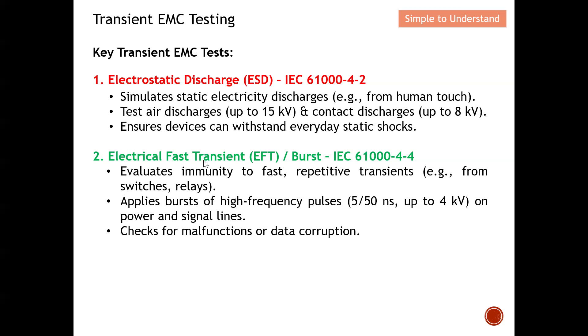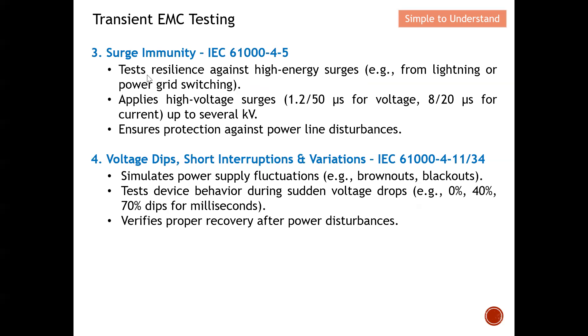This video I'm going to concentrate on the electrical fast transient — the burst standard. We need to evaluate the immunity to fast repetitive transients from switches and relays. The test is performed by applying a burst of high frequency pulses on power lines, communication lines, and signaling/control lines, and then checking for any malfunction or data corruption caused by these short-interval pulses sent to disturb the DUT.